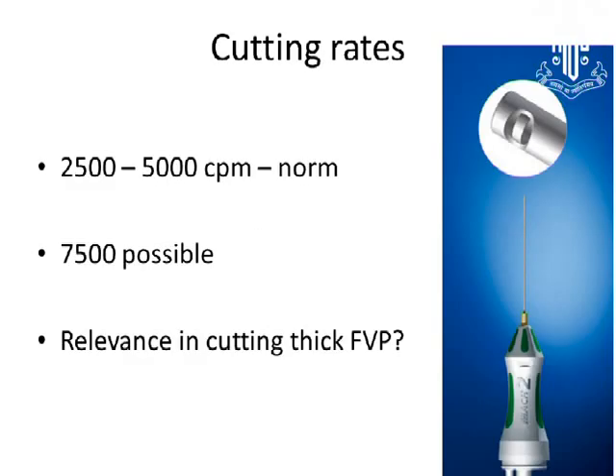Cutting rates, once again, this was touched upon. The norm right now is 2,500 cuts to 5,000 cuts per minute; 7,500 is possible. And this normal cutter which has come up is called the guillotine, like a razor blade. Usually it cuts only one end, but here they have made it cut on both ends. So when it goes down and comes up, it cuts twice. So that is a newer concept which has come up, and the port is open most of the time. So there is one modification of the cutting blade which has come up now.